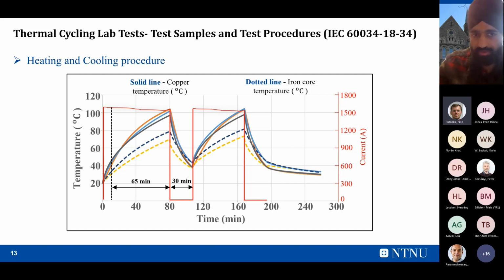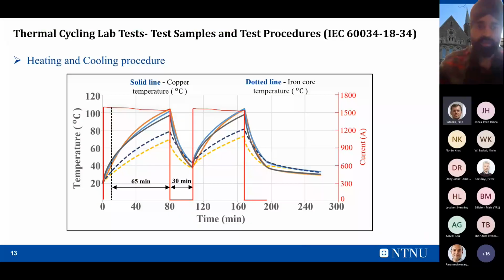So in these cycles, this dotted one is the temperature profile of the iron core, that is, of the outside steel bars. I should write it as steel bars rather than iron core. This is the outside temperature of these steel bars, the dotted one, and the solid one is the copper temperature inside. These are the drilled thermocouples inside the insulation. That's why this dummy coil is not stressed by the voltage. They are only stressed by the temperature.